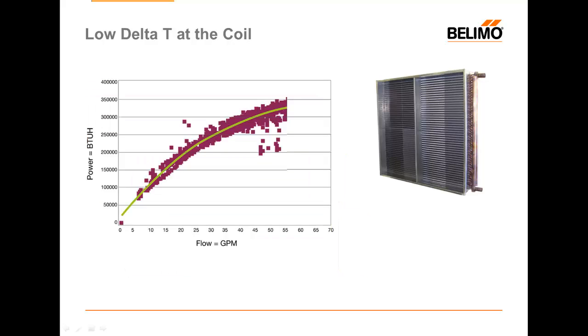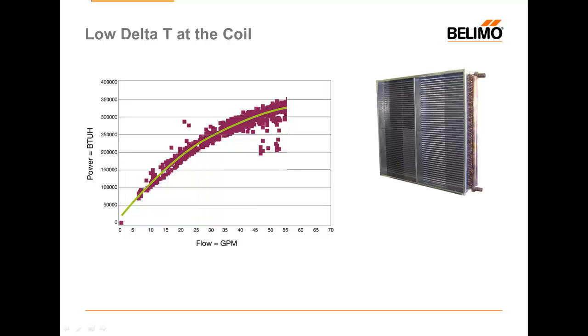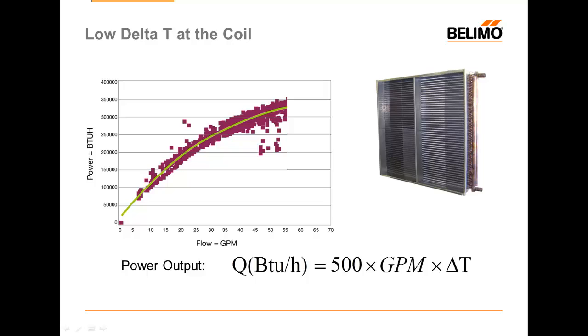Let's take a look at a coil curve and talk about how we can get into trouble here. This is a typical coil characteristic. At low flows the curve is a little bit steeper — a relatively small increase in flow generates a much higher increase in BTU. As I get up into higher and higher flow ranges this heat exchange becomes less and less efficient. Here near the top of the curve it takes a substantially higher increase in GPM to get a relatively modest increase in BTUH. This curve is governed by the formula: Power output equals 500 times the GPM times the delta T. So the load into this space is dependent on both flow and delta T.